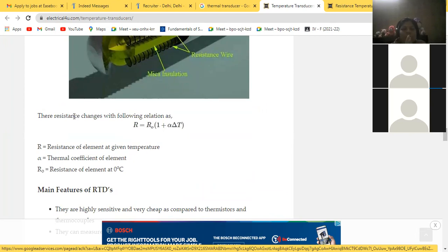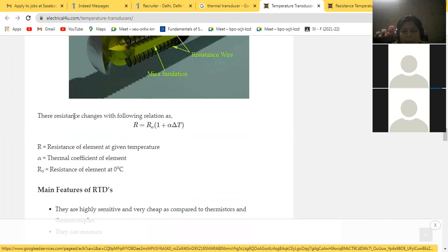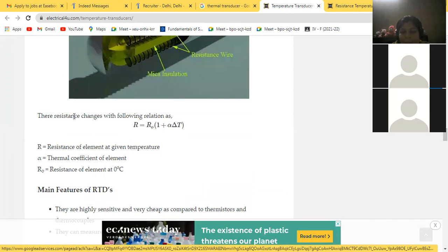Now their resistance changes with the relation R equals R naught times (1 plus alpha delta T). Delta T means change in temperature. R is the resistance of the element at a given temperature. Alpha is the thermal coefficient of the element. R naught is the resistance of the element at 0 degree Celsius.